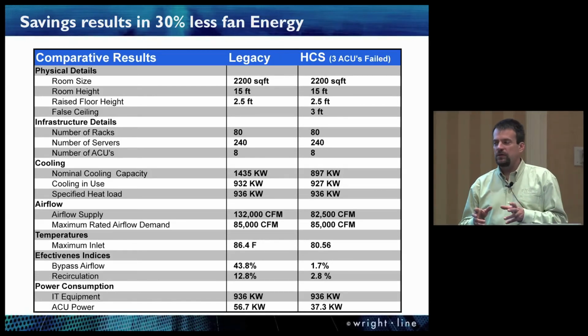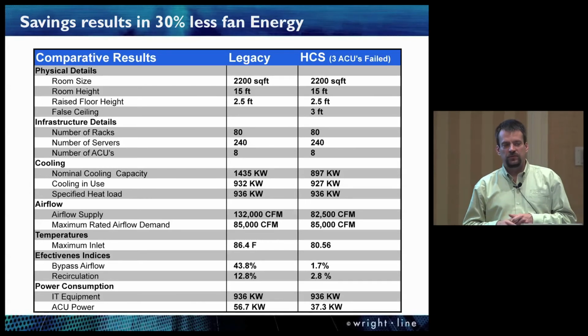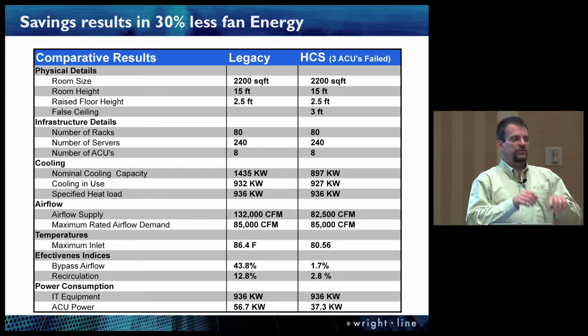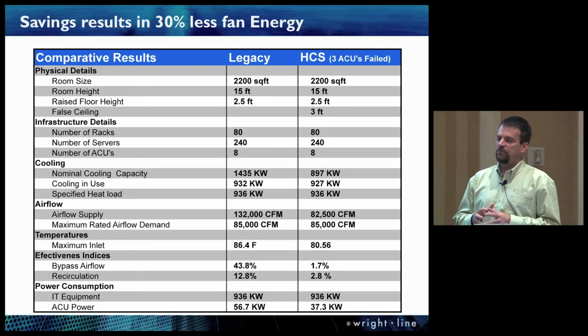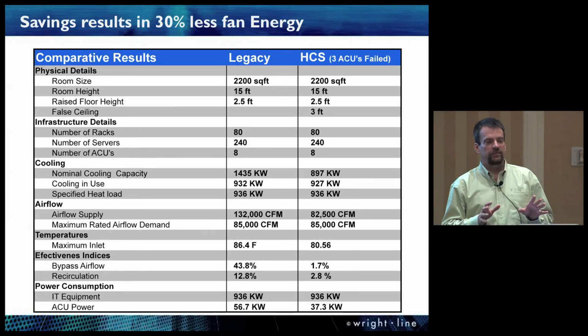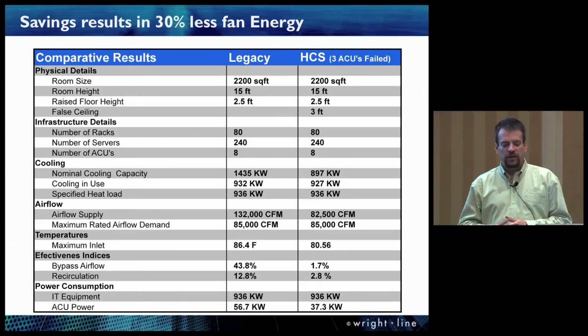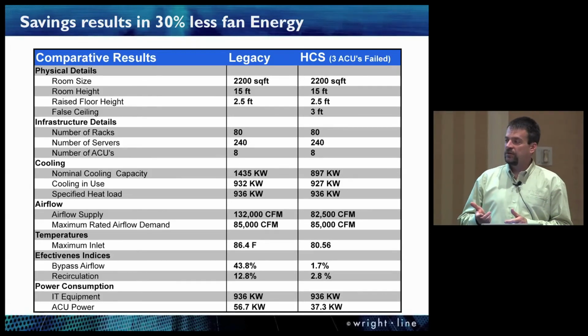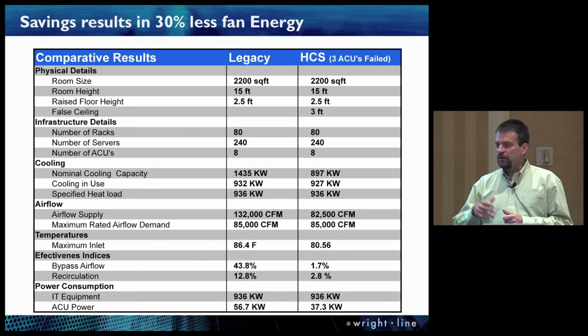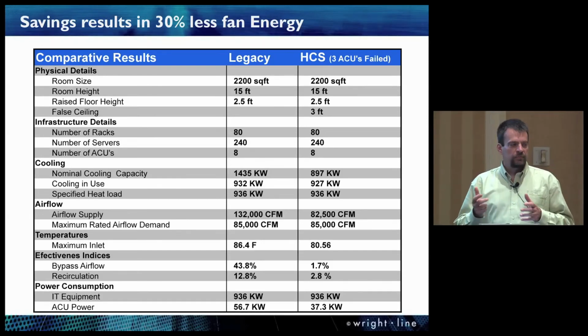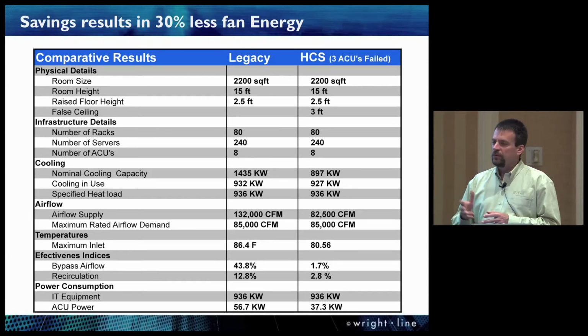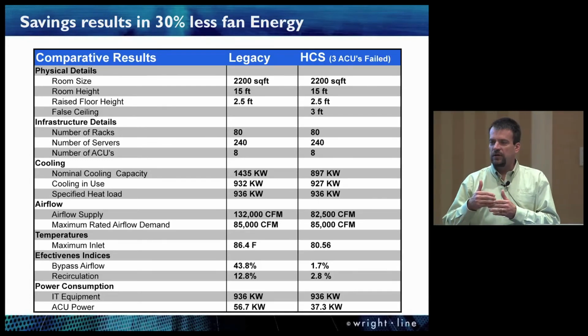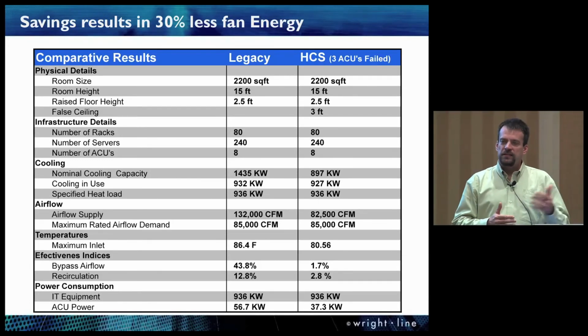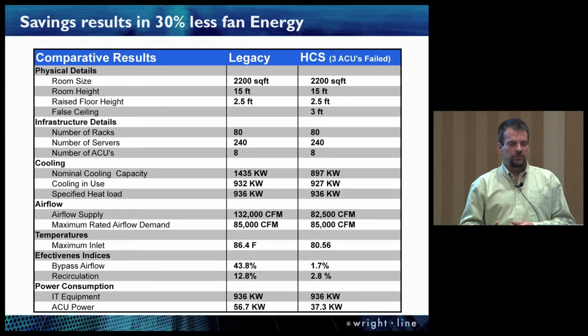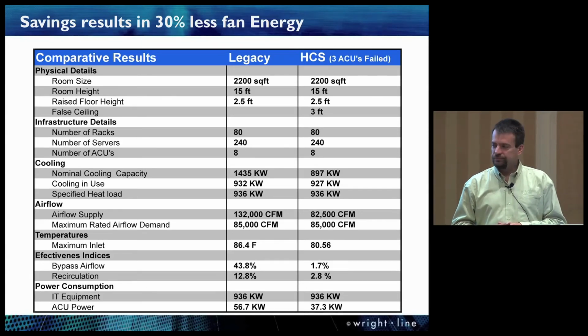And actually, if you look at it, the supply and demand is inverted. We're actually starving the IT equipment. The IT equipment is saying, give me 85,000 CFM, yet I'm only actually giving you 82.5. So I'm starving the IT equipment, granted by less than a percent or so, but the point being that you can actually match supply and demand, maintain a stable environment, keep the inlet temperatures in a predictable range, and still get the performance out of the system.